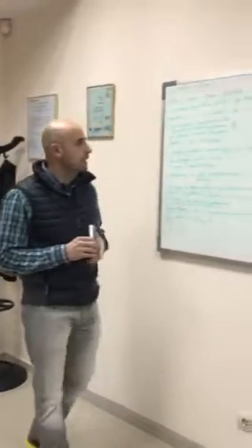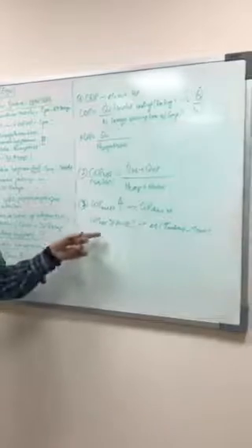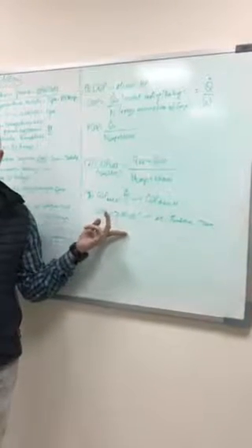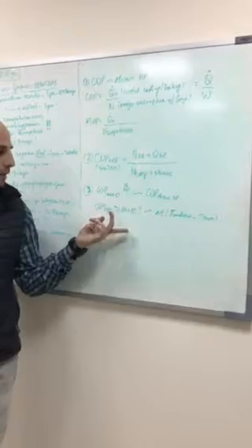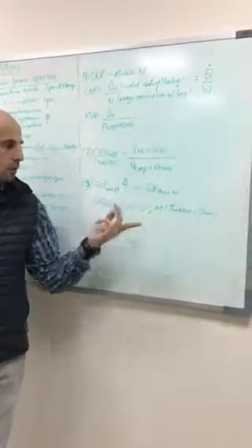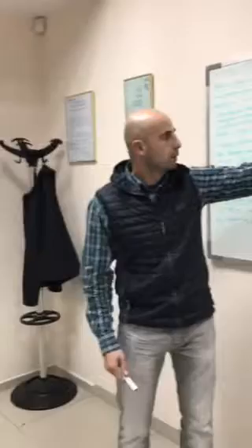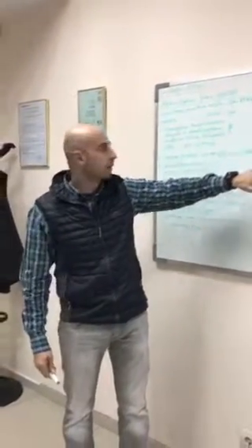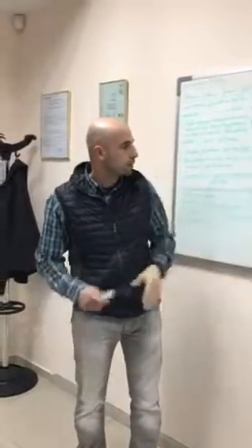And on top of that, when we talk about COPnet, don't be scared to see numbers exceeding 10 or 12, because the trick is, the higher we go with the delta T between ambient temperature and the room temperature, the higher is the efficiency of the heat recovery system, the higher is the useful capacity coming from the heat recovery, and that's how we get coefficients higher than 10, up to 12. So think very well about all these facts and make your own conclusions.